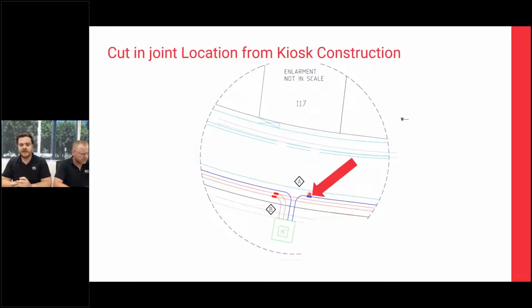So once you start to get cable PD, you do need a bit more information about the switchgear or the cable more specifically. You need to know the cable type and the length of the cable as well in order to get that distance to PD location. But once you have all that data, you're able to narrow it down really well and pinpoint where it's coming from.